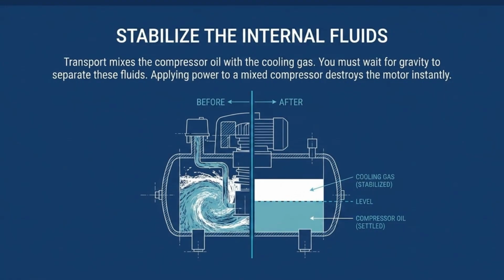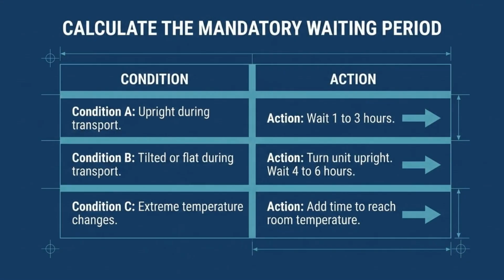Phase 2 is stabilization. During transport, compressor oil and cooling gas mix. You must allow the unit to sit so these fluids can separate. Applying power before this happens can cause immediate damage to the compressor motor. To determine your mandatory waiting period, consider how the unit was transported. If it remained upright, wait 1 to 3 hours. If it was tilted or laid flat, wait 4 to 6 hours. Always allow extra time if the unit was exposed to extreme temperatures.